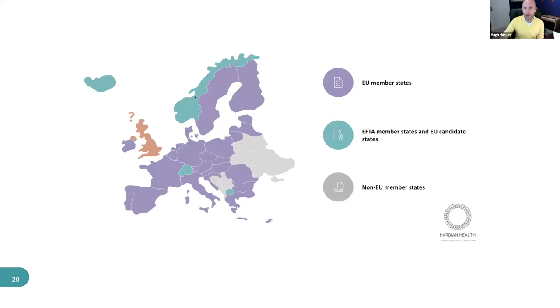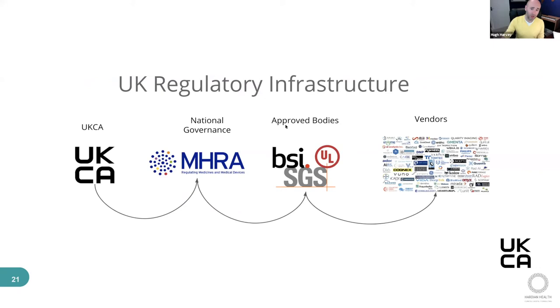Very briefly on my home turf of the UK, we don't know what we're doing. We left Europe, even though we're still in Europe geographically, and we will accept the CE mark up until June 2023. Until then, we need to write our own regulations, going to be called the UKCA, but if you lift up the hood, it's really the old MDD we're currently using. Though I'm assured there will be new medical device regulations specifically around AI as a medical device for the UK, at the moment nobody knows. If you're planning on selling into the UK and the NHS, get a CE mark for now and you're good to go. The UK regulatory infrastructure just changed the word 'notified bodies' to 'approved bodies' because we can - we're British and we like to change single words that no one else uses. There are only three approved bodies - BSI, UL, and SGS - that you can apply to for a UK CE mark currently.